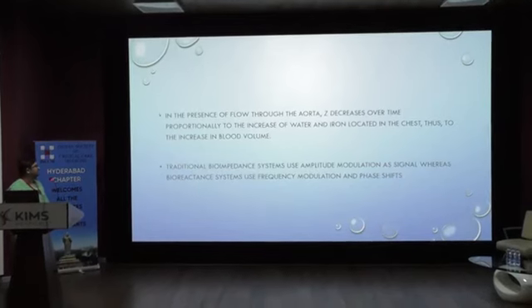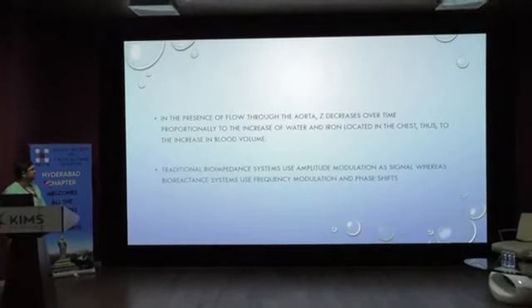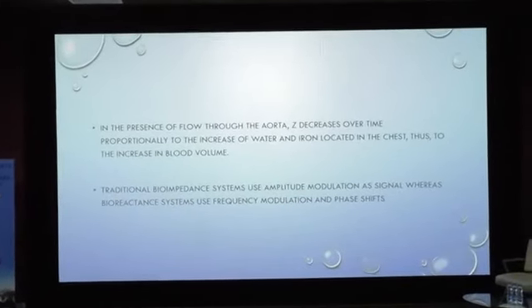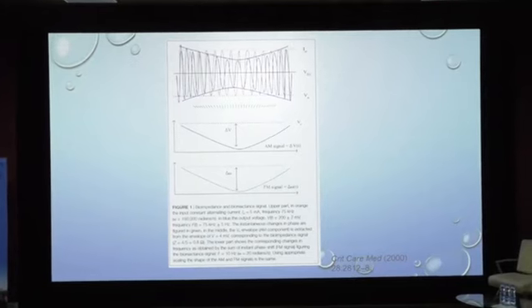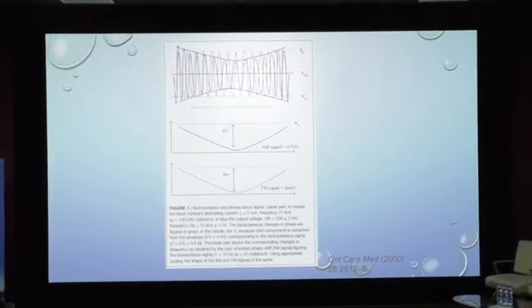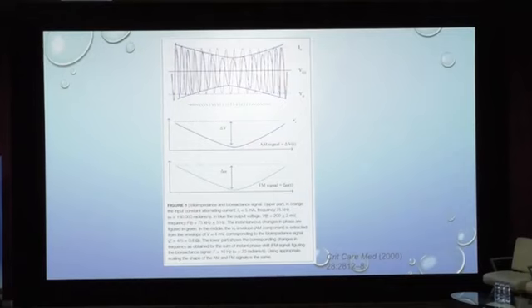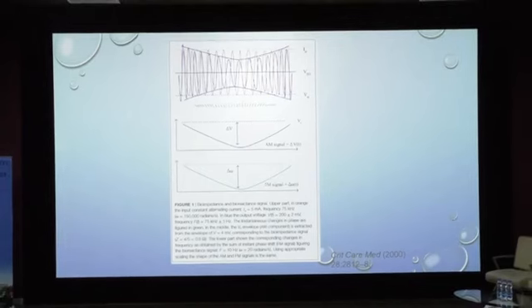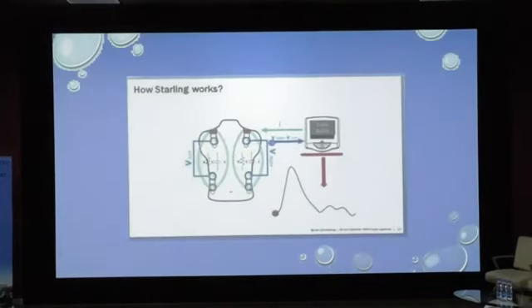Bioimpedance and bioreactance work in a slightly different manner. Bioimpedance systems use amplitude modulation as the signal, whereas bioreactance uses frequency modulation and phase shifts. There are two currents — voltage and current — flowing through the chest via electrodes, and we look for the shifts. These AM and FM signals are correlated to derive the cardiac output.